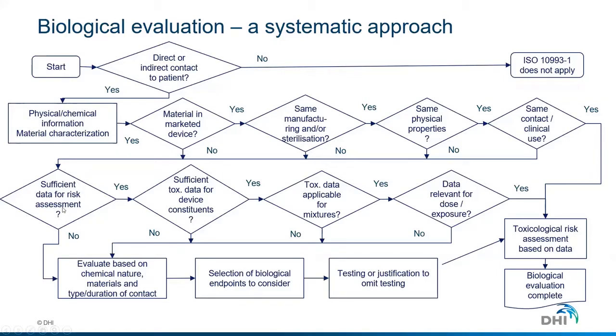Do we have data that allows us to assess the biological risks? Are there toxicological data to assess device constituents? Does it apply to mixtures? Are the data relevant? And then you can evaluate the potential risks and decide which biological endpoints to consider. Do I need to test, or can I justify omitting a test? Perform the risk assessment based on the sum of data that you have, and then document it all in your biological evaluation.